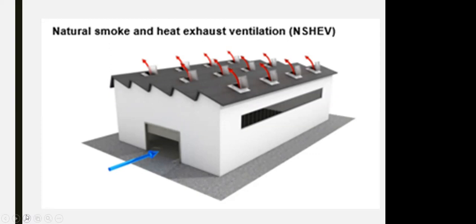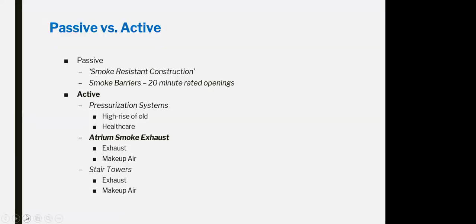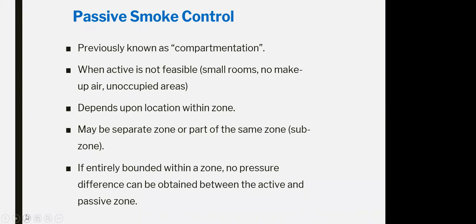The first system we have is natural ventilation. It could be applicable for above ground car parks, and for industrial areas like hangars and workshops, providing a roof access hatch on the top, working with a fusible link or motorized. In case of fire, it has to open, along with the sides of the building and the main entrance, to allow a differential pressure, allowing the flow of air so it will extract the smoke outside. This one is a passive ventilation.